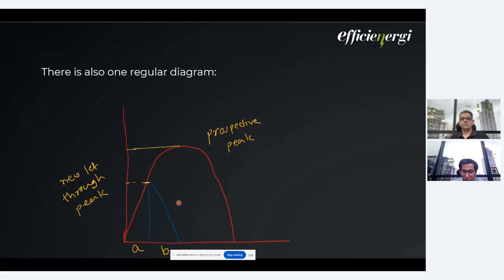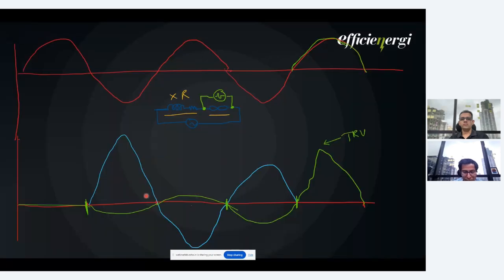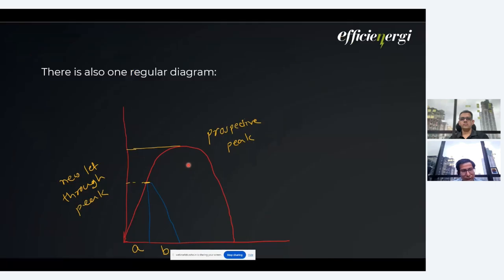You might not have seen this test and these diagrams, but this is a very regular diagram that we see for the arcing time and operating time of the fuse. This is the prospective fault current, and we basically use current limiting fuses, which start melting at a much lower value than the prospective peak. This is what we call the let-through peak of the fuse. This represents the current limiting feature of the fuse. Here the first part is the melting time, and this part is the arcing time. So A plus B comes out to be the complete operating time of the fuse.